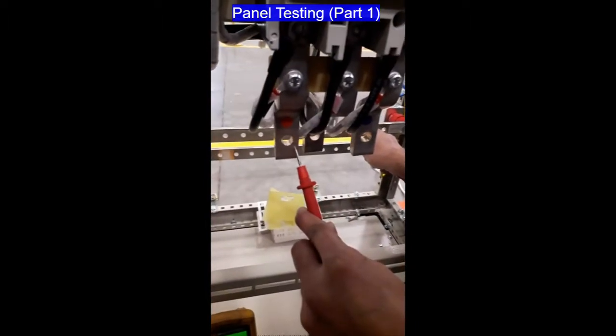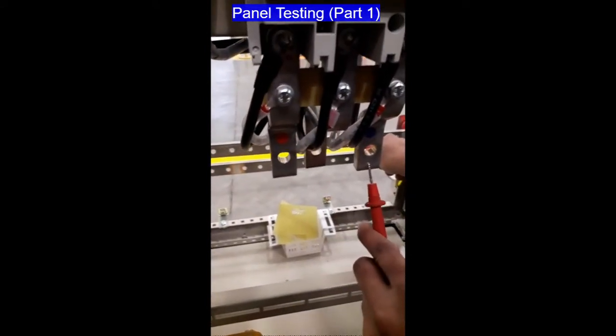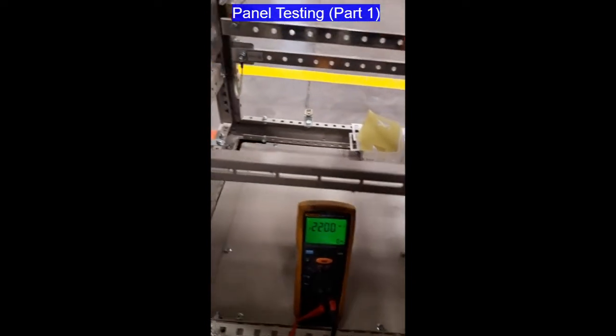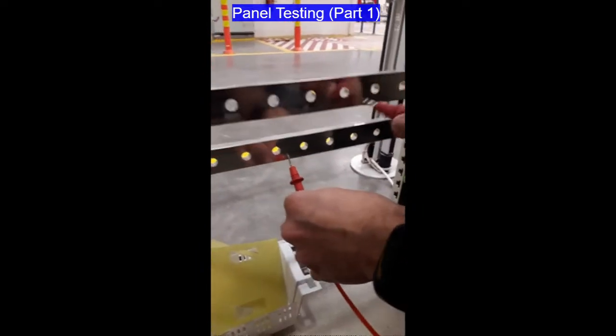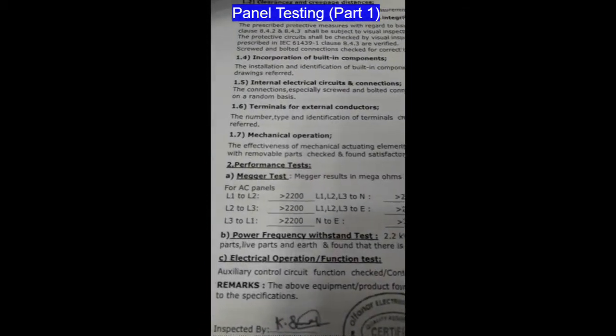Line 1 to Neutral — okay. Line 2 to Neutral. Line 3 to Neutral. Neutral to Ground — the result is greater than 2200. It's the same result as what we have in our routine test report, as you can see here in the megger test result section.